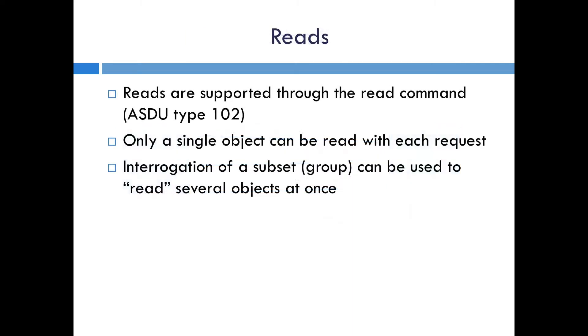There's also the capability to request a read of a particular point or a particular ASDU, supported through the read command. This ASDU type is type 102. It's important to point out that this is not one of the application functions per se — it's one of the commands which is supported. Only a single object can be read with each read request, so really in order to read a lot of different objects it's better to do an interrogation, either as a subset or as a complete general interrogation.